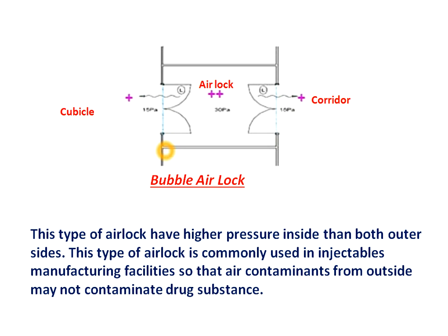This type of airlock is mostly used in injectable plants. In injectable plants there are fewer chances of cross-contamination because no particles are generated, but there is a high chance of biological contamination. Since there is high human movement in the corridor, humans generate more biological germs. To avoid these germs entering the cubicle — the injectable manufacturing area — the airlock is kept at higher pressure than both the corridor and cubicle, so air flows outward from the airlock to both sides, separating the two areas.